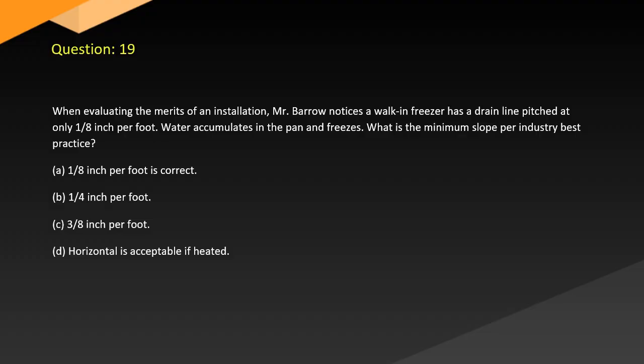Question 19. When evaluating the merits of an installation, a technician notices a walk-in freezer has a drain line pitched at only 1/8 per foot. Water accumulates in the pan and freezes. What is the minimum slope per industry best practice? A. 1/8 per foot is correct. B. 1/4 per foot. C. 3/8 per foot. D. Horizontal is acceptable if heated.